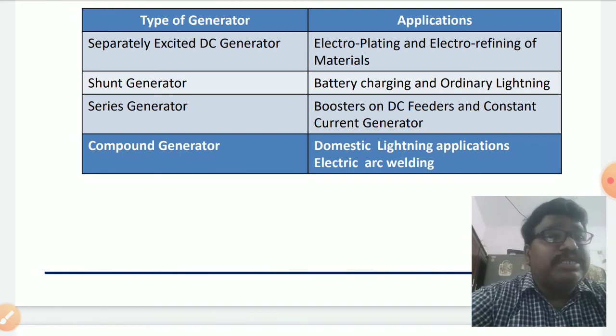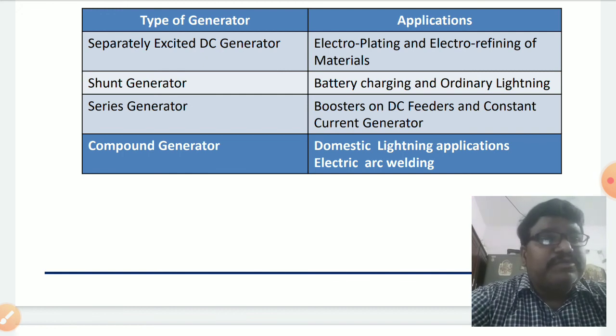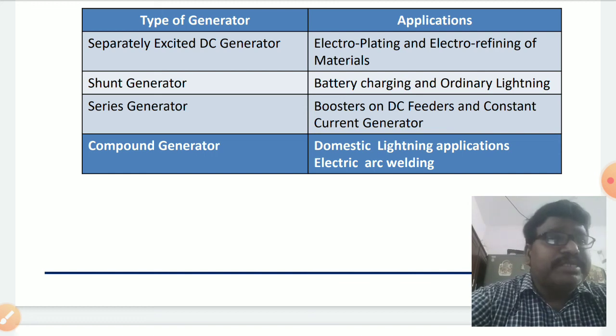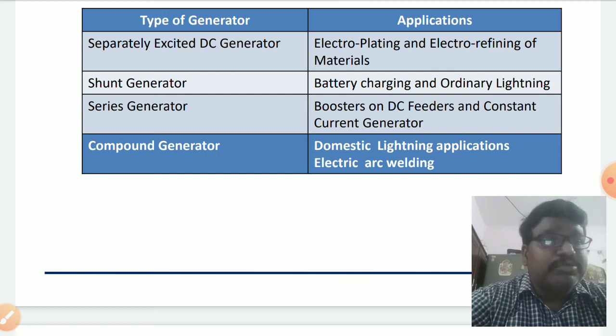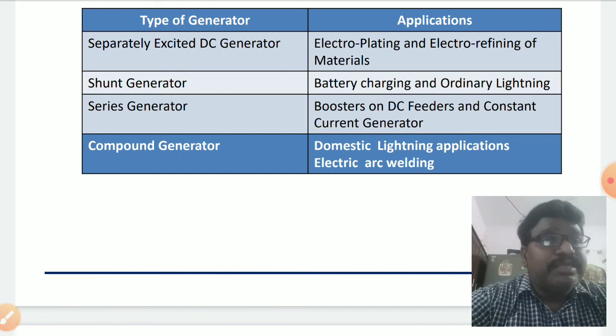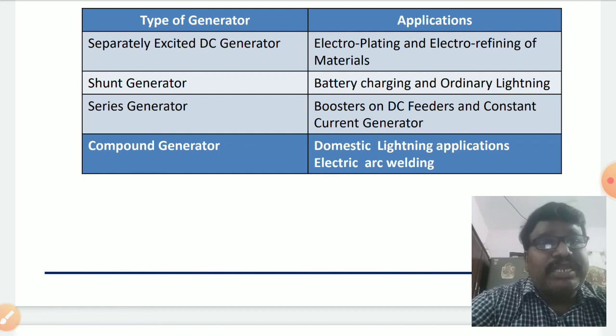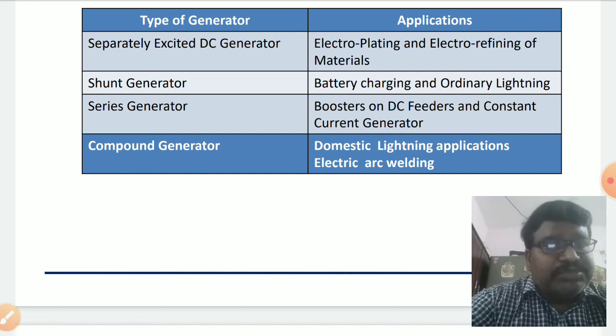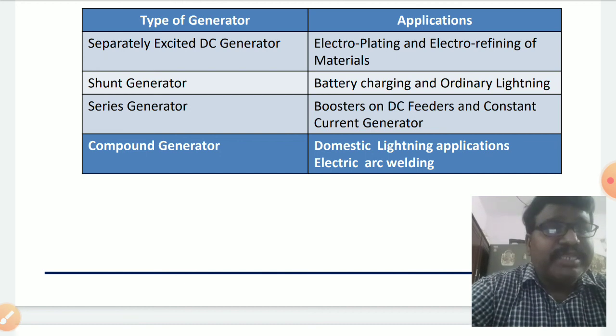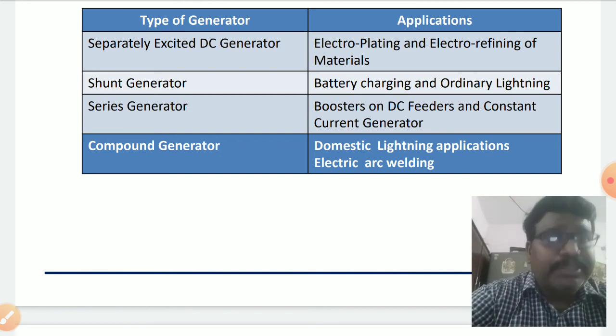The cumulatively compound generator generates rated voltage with only a slight variation, and is majorly used in domestic lighting applications. The differentially compound generator, where series field flux and shunt field flux are in opposite directions, is used for electric arc welding, as it supplies constant current for welding applications. These are the various applications of DC generators.